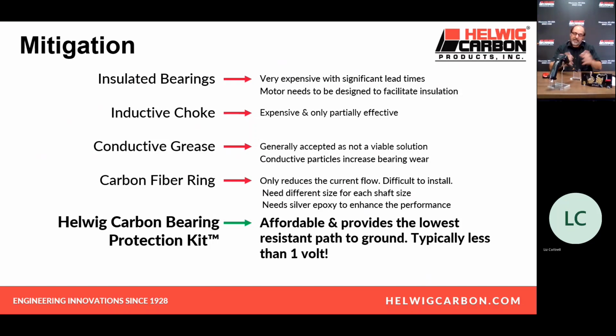Insulated bearings. You can insulate the bearing from the motor case and prevent arcs through the bearing, and it works. However, it's a very expensive solution, and you have done nothing to prevent the arc from common mode voltage occurring elsewhere. Remember, it's going to look for the path of least resistance. If it isn't through your bearing, it's very likely through the gearbox that's connected to it when the gears lock up, or other downstream connected equipment. Just because you've insulated the bearings and saved the motor bearings does not mean you have reduced the problem of arcing internal to the motor or from connected equipment downstream.